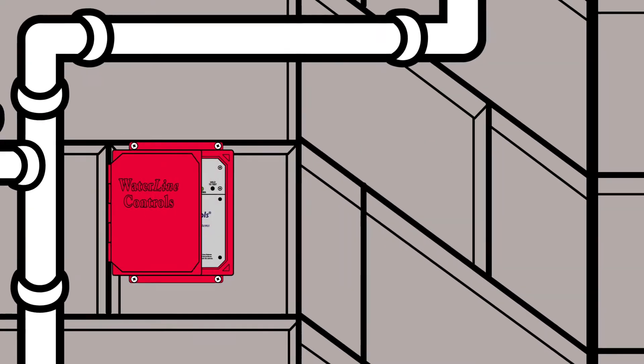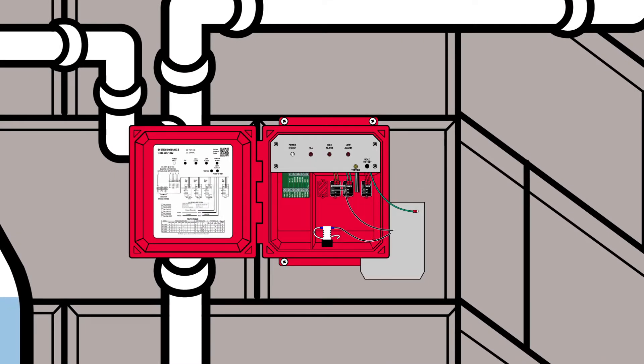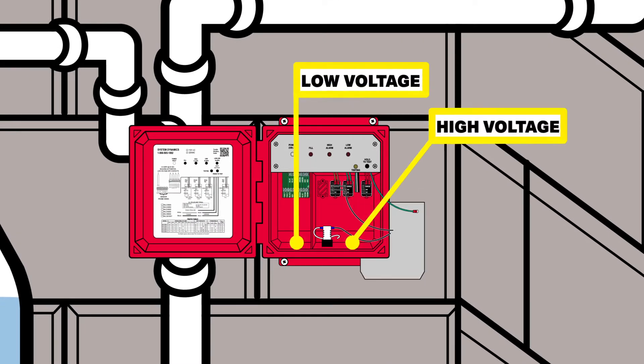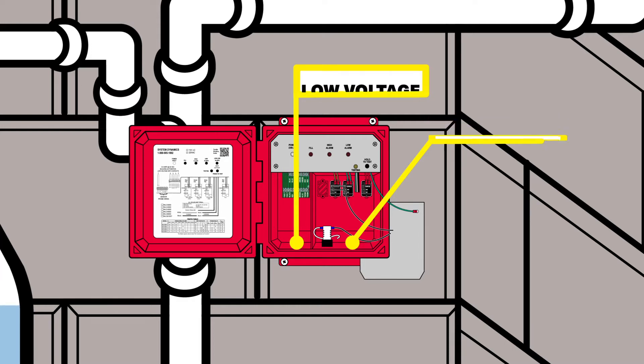When running metal conduits, keep note of the high-voltage and low-voltage compartments in the waterline panel. It's important to not have low-voltage conduits run parallel to high-voltage conduits without proper spacing in order to avoid inductive electrical interference.